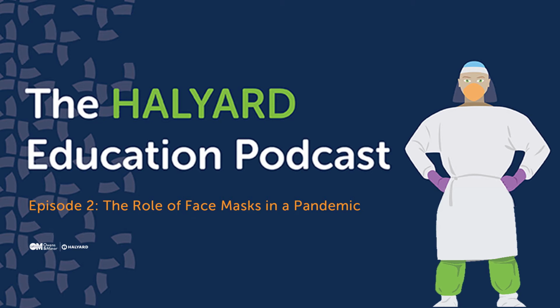Respirators do have a different set of standards. They are much more stringent since they were intended to protect the worker from much broader range of hazards. But the big differences are how they measure filtration and breathability. So for instance, medical masks are measuring filtration using a BFE test, which measures a 3-micron particle at a relatively low breathing rate. But respirators measure a much smaller particle at a much higher breathing rate. And they have to show some ability to seal to the face. So you get a much better filtration of the air when you inhale as opposed to just capturing stuff when you exhale.